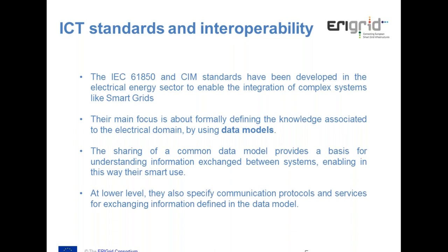Of course, the lower level, which I was talking about, so the specification of communication protocols and actual concrete means of exchanging information, is also specified by these standards. In particular, 61850 defines different communication protocols for exchanging information between devices. CIM defines the communication protocols oriented towards the integration of systems at the enterprise level. I will talk more about this later. But in any case, they also define ways for actually exchanging this information, and they also add this higher-level information in the form of data models.